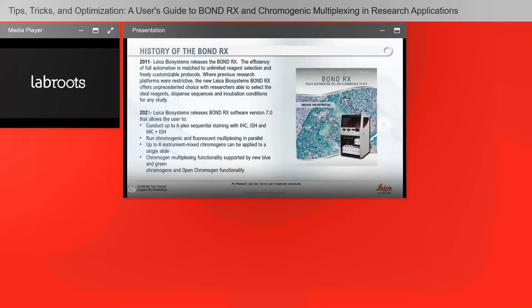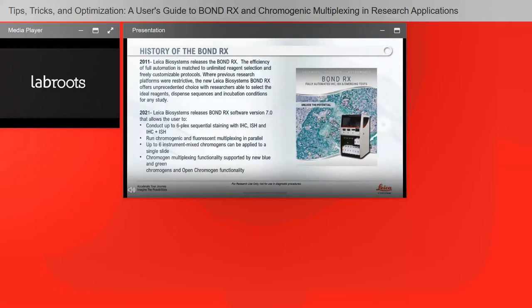With IHC, ISH, and IHC plus ISH, you can run chromogenic and fluorescent multiplexing in parallel — one chromogenic assay, one fluorescent assay running at the same time on the Bond RX. You can do up to six instrument-mixed chromogens applied to a single slide, including chromogens from outside companies. The chromogenic multiplexing functionality is supported by new reagents — in particular the blue and green chromogens — and also open chromogen functionality using a new detection system.